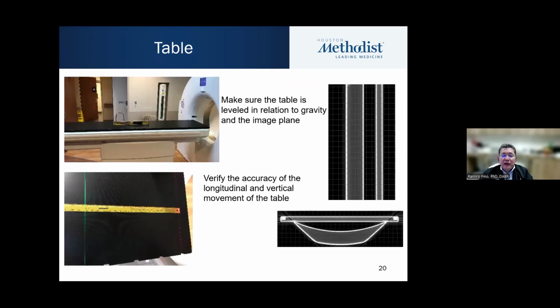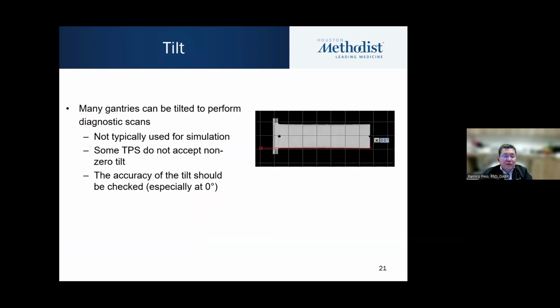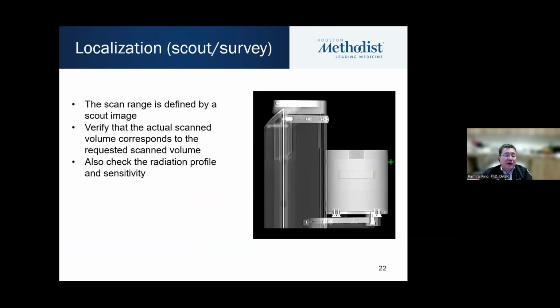Typically, we'll want the table to be leveled in relation to gravity. That's easy to measure. Typically, use a level. We need to verify the motion of the table, and typically in vertical and longitudinal motions. Many scanners have the ability to tilt, not typically used in simulation, and even some treatment planning systems do not accept non-zero tilt. So it's important that the accuracy of the tilt is checked for the scanner. The scout and survey needs to be checked, and we need to verify that actually what we're planning to scan is actually the correct volume.